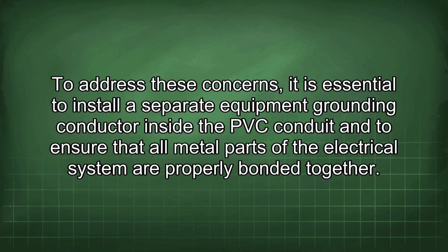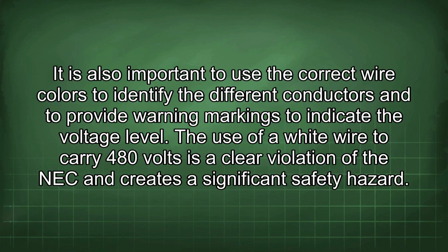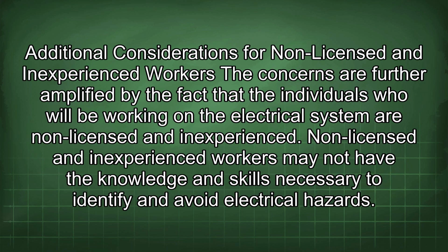To address these concerns, it is essential to install a separate equipment grounding conductor inside the PVC conduit and to ensure that all metal parts of the electrical system are properly bonded together. It is also important to use the correct wire colors to identify the different conductors and to provide warning markings to indicate the voltage level. The use of a white wire to carry 480 volts is a clear violation of the NEC and creates a significant safety hazard. Additional considerations for non-licensed and inexperienced workers.